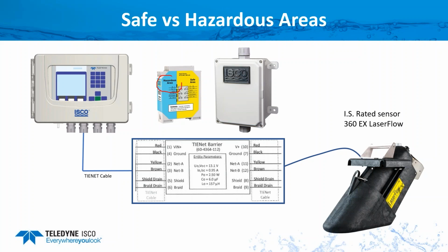And essentially what the IS barrier does, it acts like a fancy fuse. What I mean by that is that if there was a power surge in the controller due to AC power surge or lightning or something, the power would not be able to transfer through that barrier. It's going to hit that barrier, it would actually open up and then eliminate sending the power down into the sensor. So if we block the high current or power from going to the sensor, it eliminates any chance for a spark or explosion in the sewer.